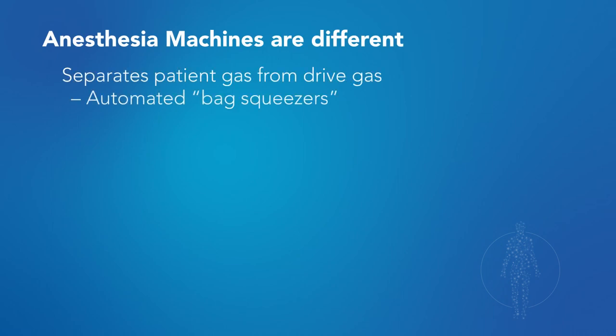There are some important differences, though. The anesthesia machine has a breathing system very different from that of an ICU ventilator. Think of how an anesthesiologist squeezes a bag to ventilate a patient's lungs—anesthesia ventilators are really more like automated bag squeezers. There's the patient gas that the patient breathes, and what's called drive gas, which the ventilator pumps into a chamber to essentially squeeze a bag. That's how most anesthesia breathing circuits are built.